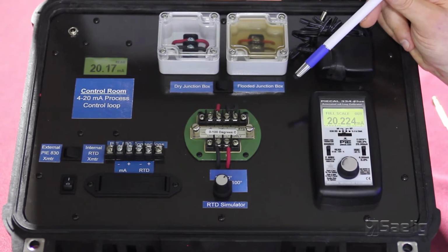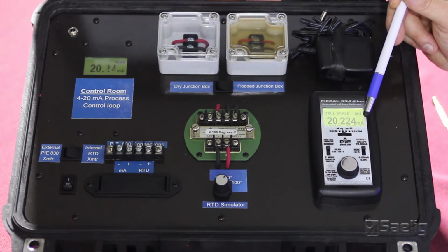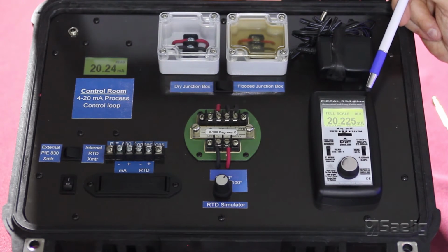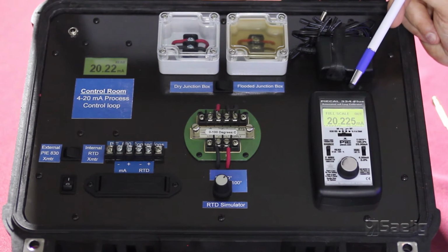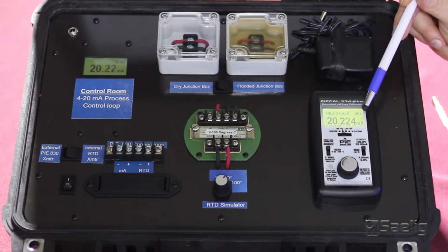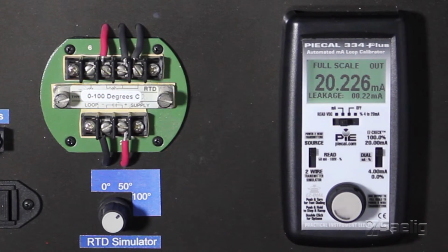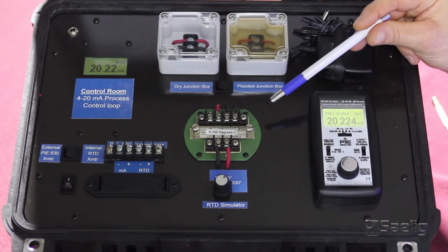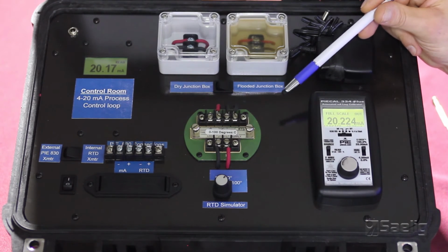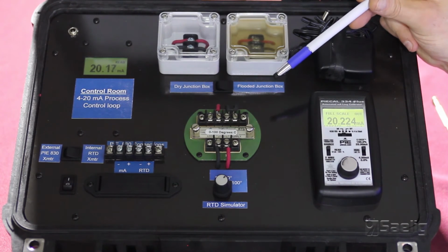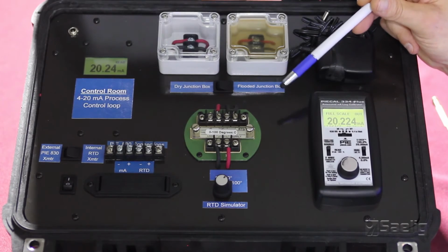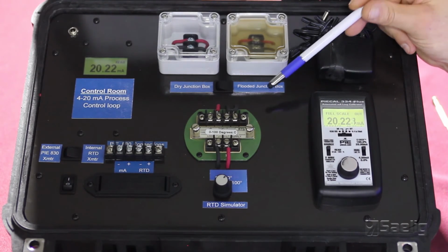Only the Piecal 334 Plus or Piecal 434 or several of our multifunction calibrators have our patented current leak detection. By having it displayed on the unit itself, a technician will not have to go out and try to change transmitters only to find that the problem still exists. That concludes our discussion today on Piecal milliamp calibrators and our current leak detection.